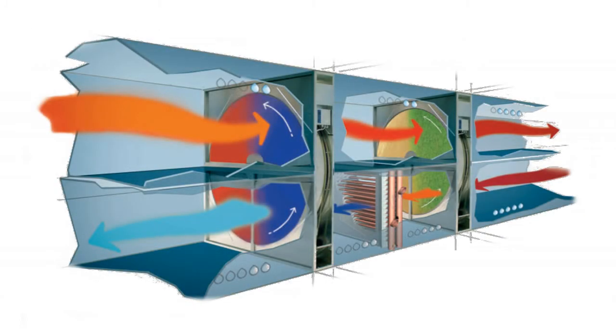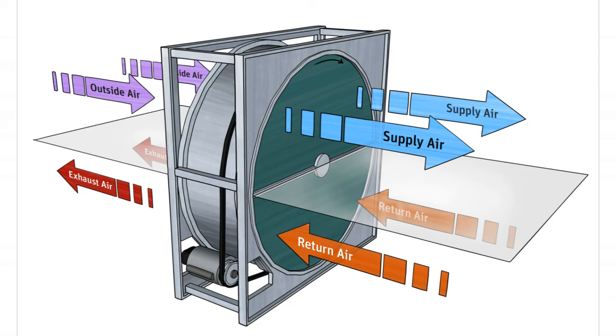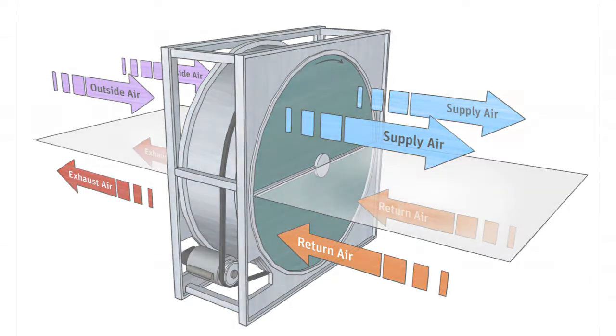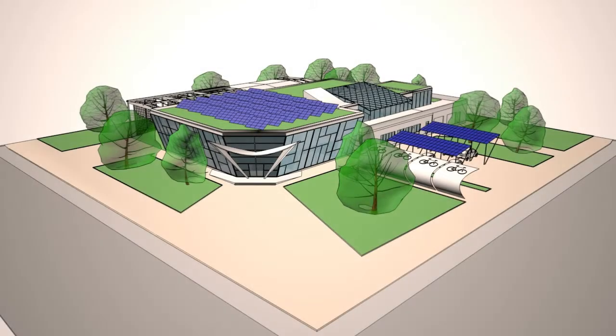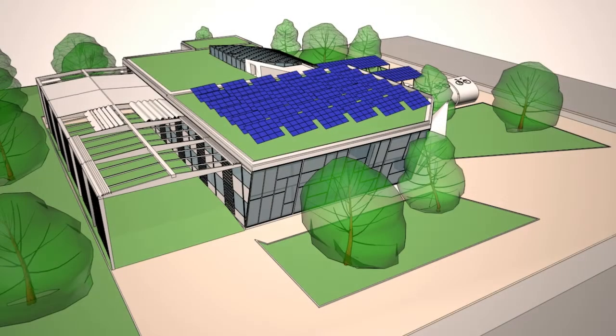Dedicated outdoor air system with heat recovery equipment is used to constantly provide 100% freshly treated outdoor air to the occupants whilst recovering sensible heat from the return air with the heat recovery wheel. Implementing large transparent surfaces to the facade, window-to-wall ratio of 40%, we minimize the need for artificial lighting.